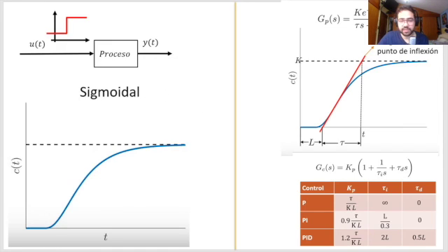It's very simple. We have our function. So with this graph, we see the blue point, and where it's stabilized is where we have the gain. So we have K. We make a tangential line. From the start to the end, we have the tau, and the time it takes to start that tangential line is L. Then we have this table. It depends on which controller you are using. Now we're using a PID, so we need these values to generate this function.